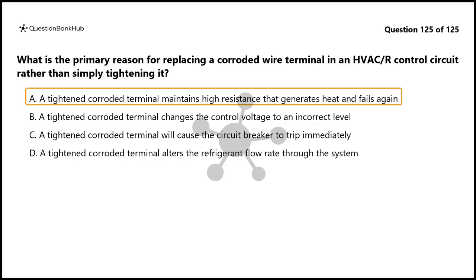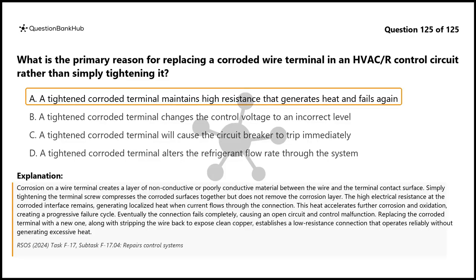The correct answer is A. Corrosion on a wire terminal creates a layer of nonconductive or poorly conductive material between the wire and the terminal contact surface. Simply tightening the terminal screw compresses the corroded surfaces together but does not remove the corrosion layer. The high electrical resistance at the corroded interface remains, generating localized heat when current flows through the connection.